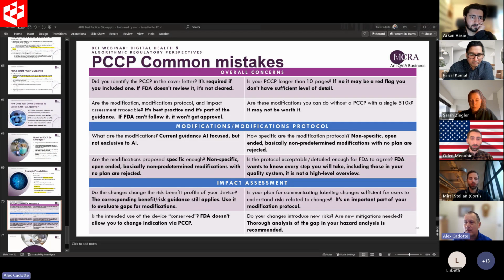modifications and overall concerns, it used to be people didn't know they had to identify the PCCP in the cover letter for the submission. FDA now has in the final guidance basically a list of things that you have to do in order for FDA to recognize the fact that the PCCP is part of your submission. If you include it and it's not obvious that it's there and FDA discovers it later, it's not cleared.